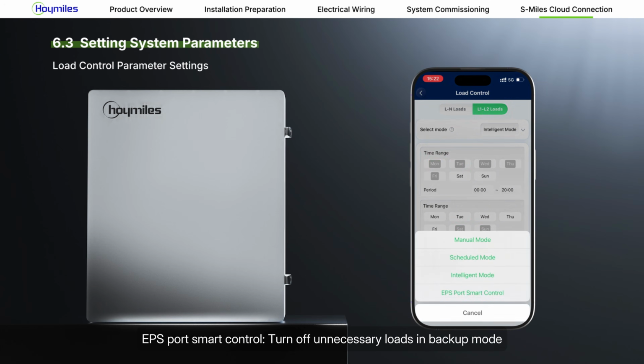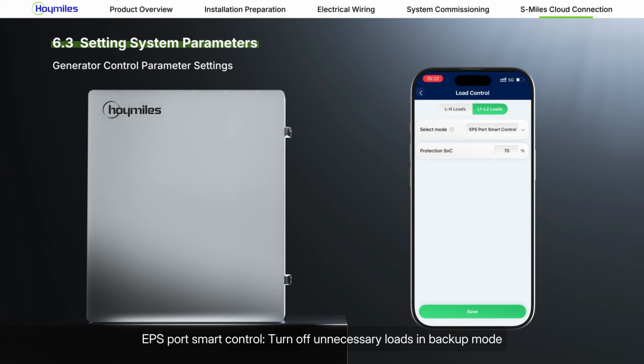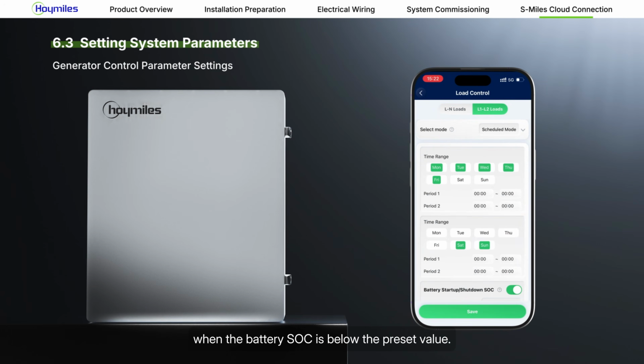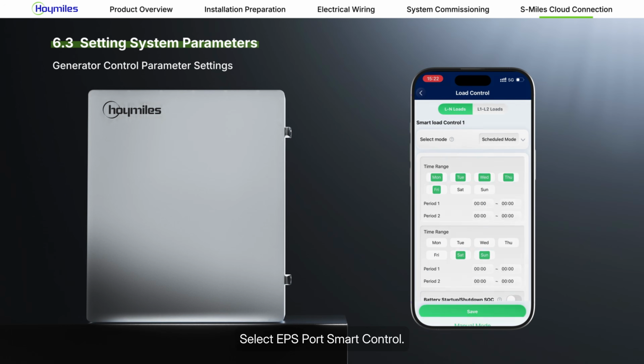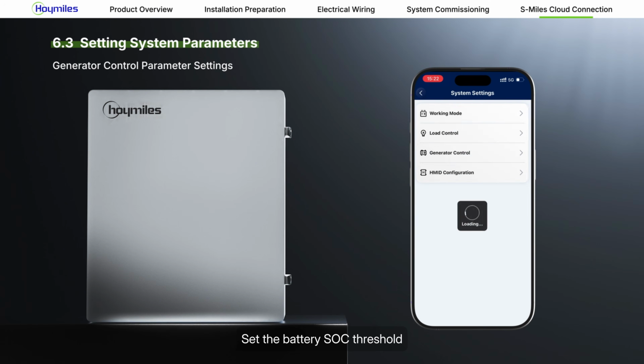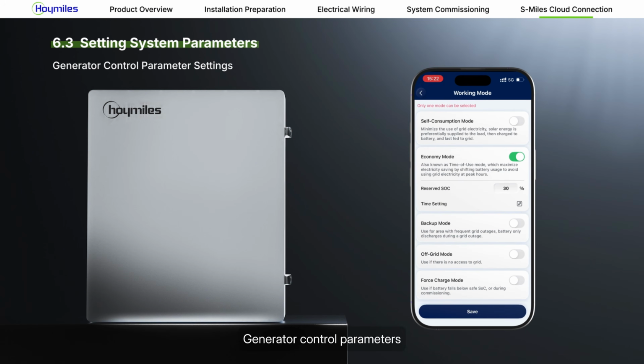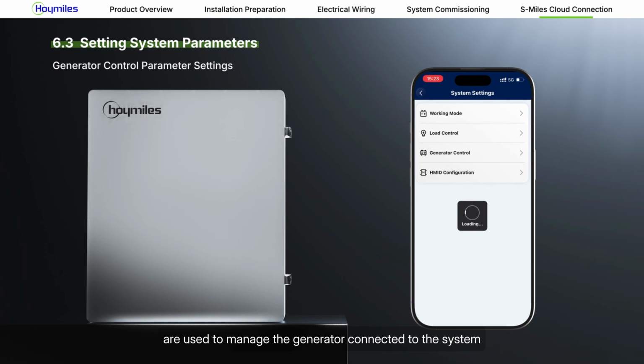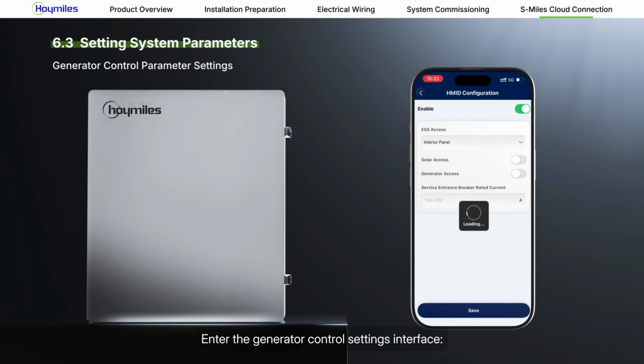EPS Port Smart Control: turn off unnecessary loads in backup mode when the battery SOC is below the preset value. Select EPS Port Smart Control. Set the battery SOC threshold. Click Save. Generator control parameters are used to manage the generator connected to the system and ensure its operation as expected in different modes. Enter the generator control settings interface.